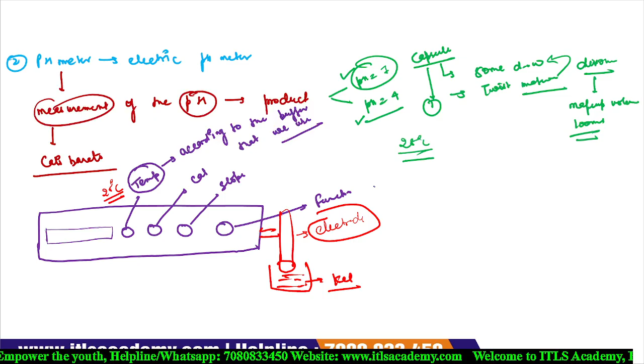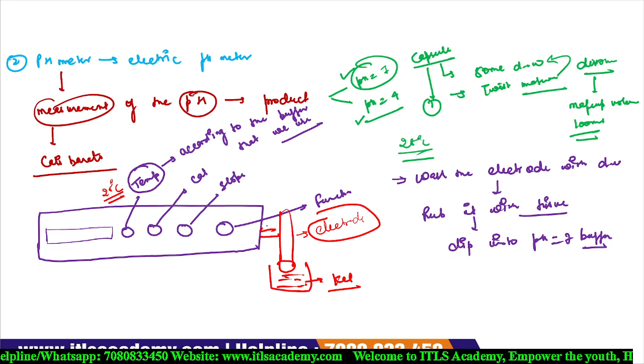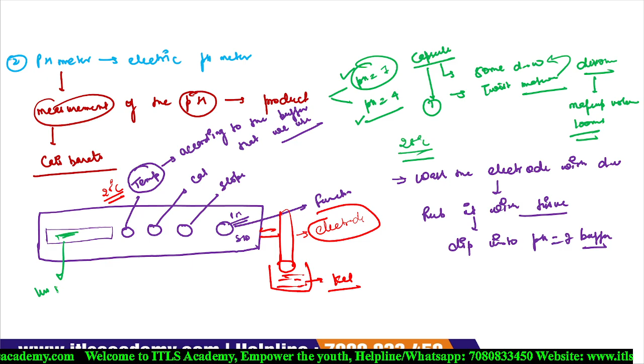Remove this electrode from the KCl solution, and wash the electrode with distilled water. Then rub it with the tissue paper. Then dip it into the pH 7 buffer. When you dip it into the pH buffer, just move this function key from the standby to the pH. Now here some value is shown which is less than 7. Now what you have to do, you have to move this knob in a clockwise direction. Okay, which knob? That is your cal knob.